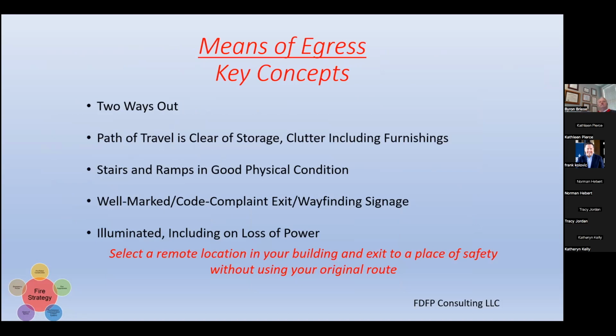Means of egress, like I said, clutter is our enemy. So I challenge you to walk to a remote location in your building and exit to a place of safety without using your customary route. Try that out in your building. Go to an obscure place and go to a place of safety and note what you see in that path of travel. Is it clear or is it cluttered? Are the ramps and stairs in good condition? Do you have proper signage? And what would happen if you lost power? Ask yourself those questions in a 5 or 10 minute self-drill on what your building's means of egress look like. This is gelling down from multi-inch code books on the life safety code. But at the level of building operation, if you do these things, you'll get a good idea whether you're in good shape or you have a significant problem.